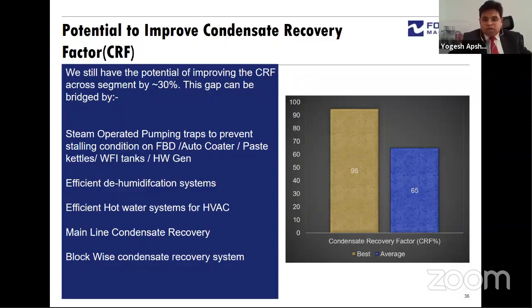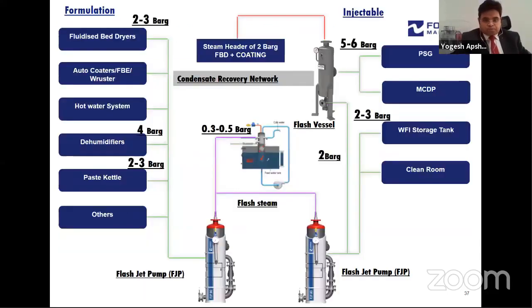In these composite pharmaceutical formulation plants, we have seen that the layout of the pharma plant is quite big. In those plants, we have given equipment-wise or block-wise condensate recovery systems, and we have delivered the condensate up to a distance of almost 1 kilometer. So it is a very important aspect. Condensate recovery is a very important aspect of any steam system.